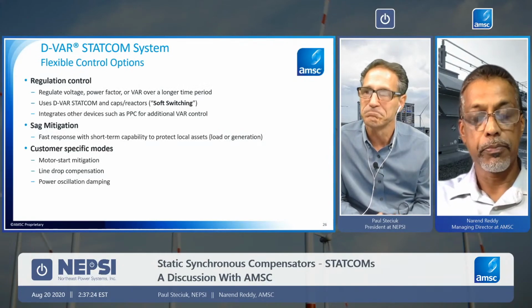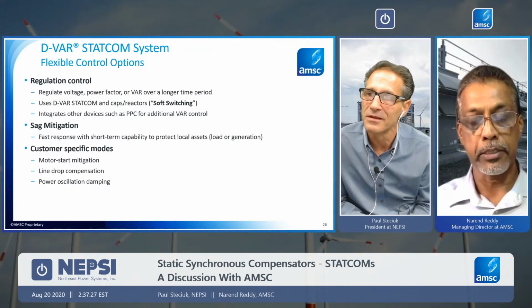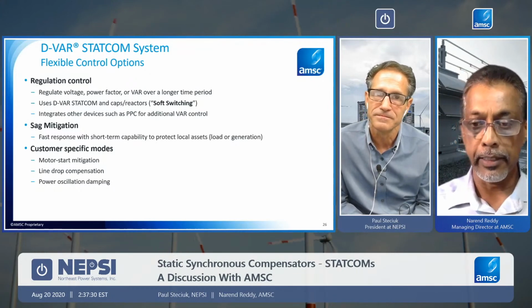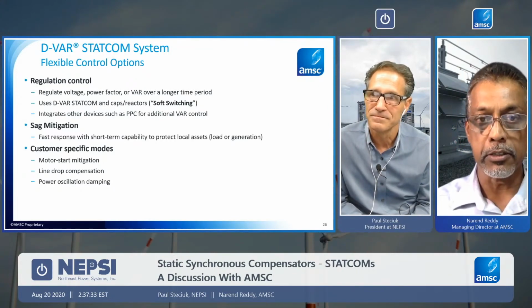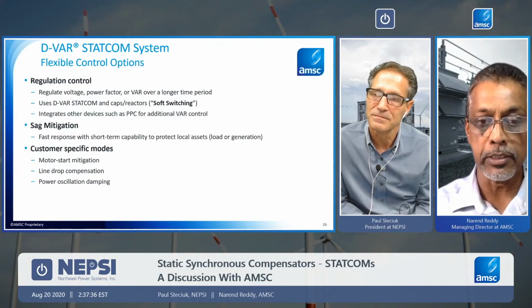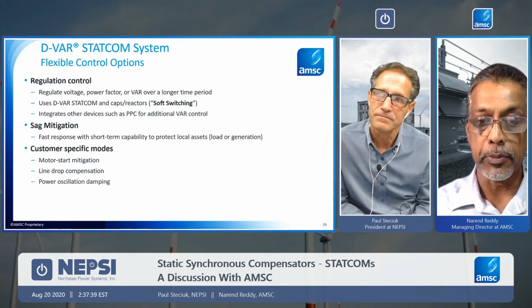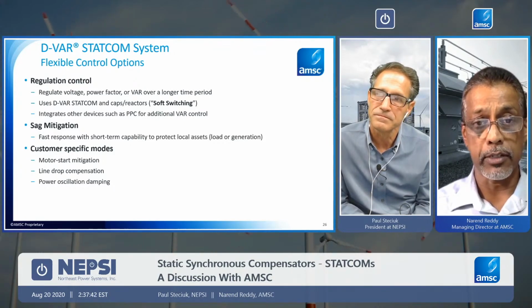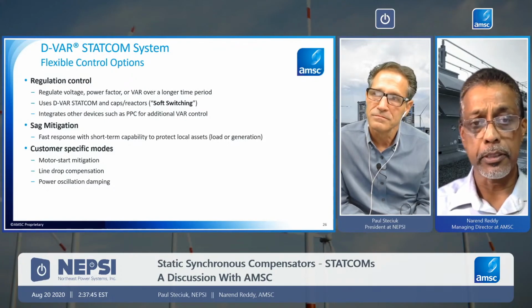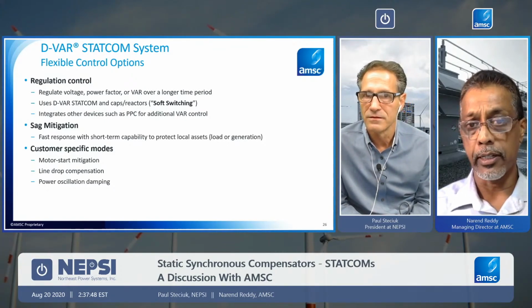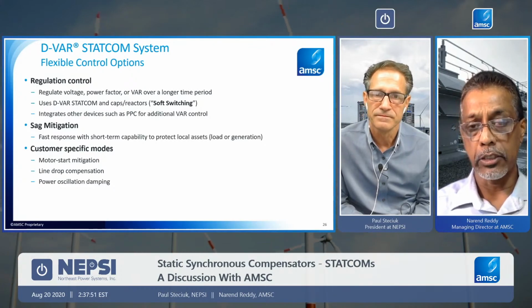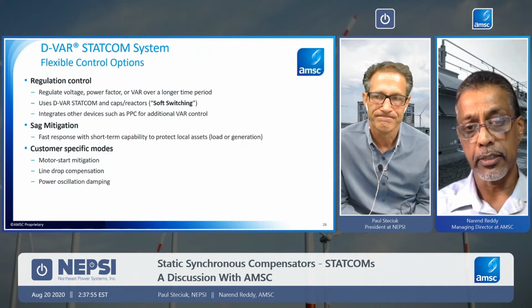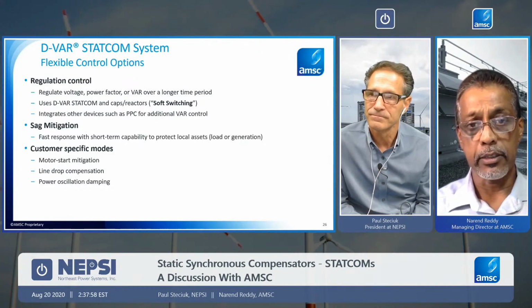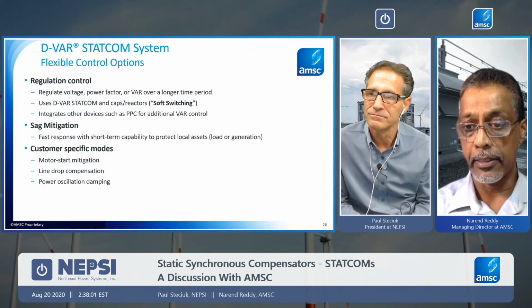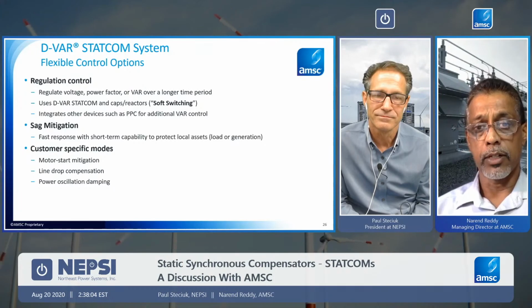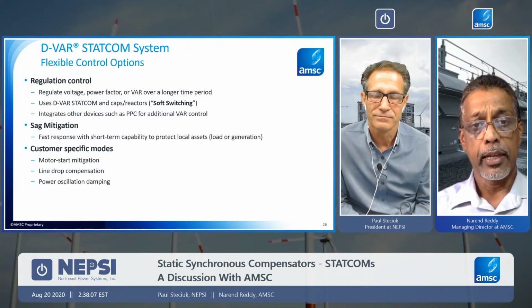Sure. If I may just start from a basic perspective of controls, at the end of the day, yes, it's a current control device, but it must meet the customer's expectation for what the problem is and must be able to solve that. In terms of a performance requirement, it could be to regulate voltage or regulate power factor or VAR, whatever that is. Really, the STATCOM device, as I mentioned earlier on, is very akin to a synchronous machine, and it can do the same level of volt control functionality at very high frequency.